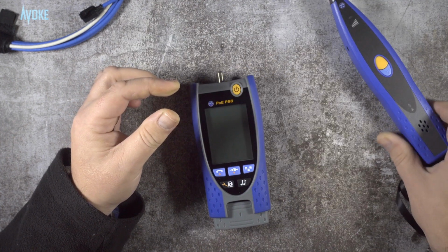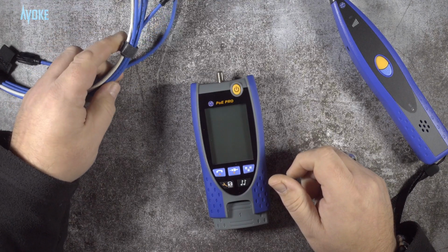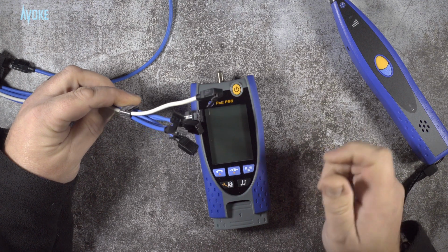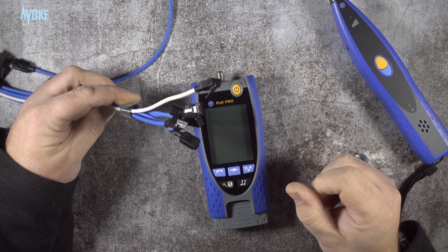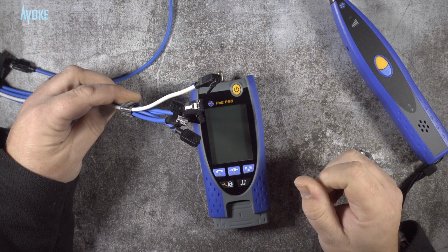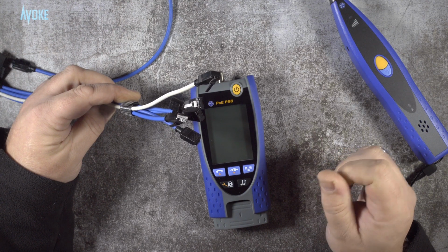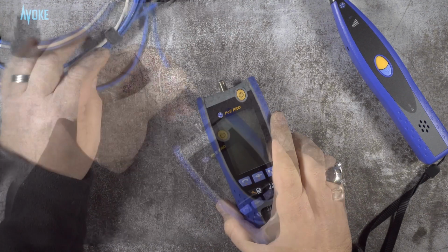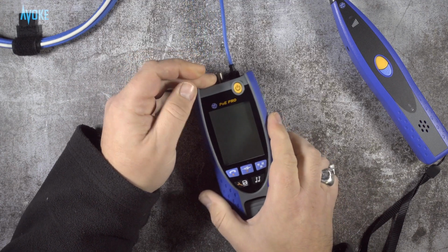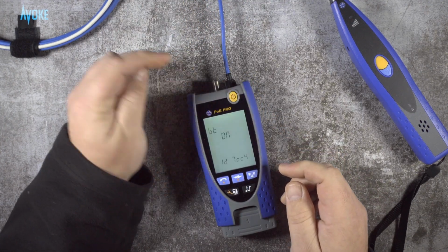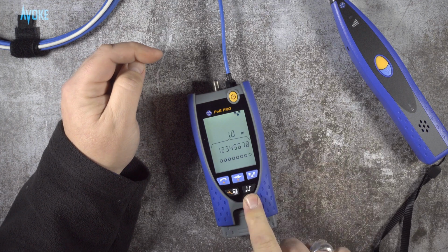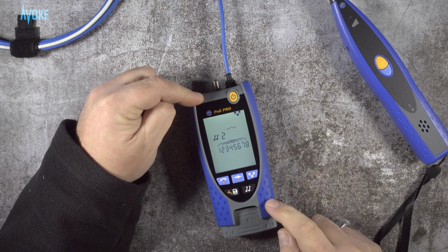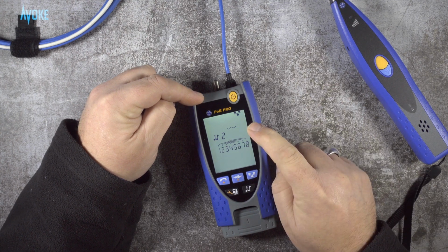Now, what I've done is I've set up a group of cables, unlabeled, and I've got no idea which one that I need. So in this scenario, let's say you've got a network cable running from the kitchen, running back, and that needs to be connected to the network switch. So you take your PoE Pro, you go into the kitchen, you plug into the network port in the kitchen, you turn on the PoE Pro, you press the musical notes button, and now this has changed the PoE Pro to emitting a tone down the cable.